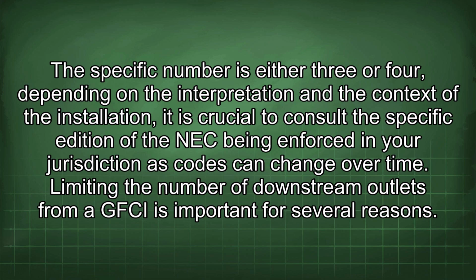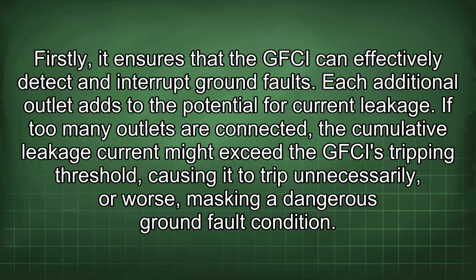Limiting the number of downstream outlets from a GFCI is important for several reasons. Firstly, it ensures that the GFCI can effectively detect and interrupt ground faults. Each additional outlet adds to the potential for current leakage. If too many outlets are connected, the cumulative leakage current might exceed the GFCI's tripping threshold, causing it to trip unnecessarily, or worse, masking a dangerous ground fault condition.